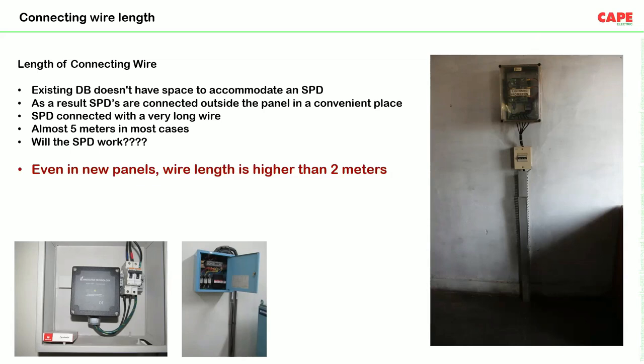Okay, now these are the various examples of an SPD. How an SPD now generally is connected in our system. Sometimes people don't have a space in the existing DB. So what they do is they put the SPD in a next DB. And in that case, wire length can be as high as 5 meters. Even in my practical experience, I've seen wire length even up to 10-12 meters. And you can just imagine, for 1 meter, voltage drop was that much. For a 12 meter cable, how much will be the voltage drop?